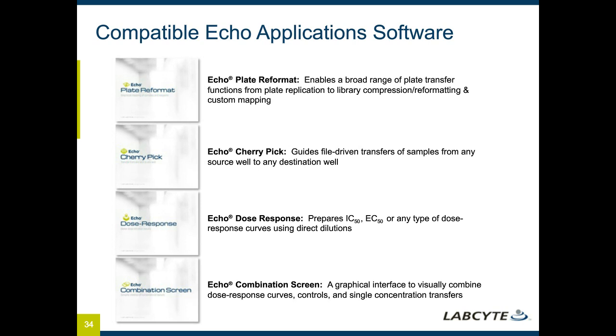And we have a software specific to Echo Dose Response, so it enables you to very quickly and easily create the different dilutions through that direct dilution process for your IC50 or EC50 types of experiments and generate those dose response curves depending on the number of points that you want and the concentrations that you determine are necessary. And then lastly, for situations where you're looking at the interaction between different drugs potentially, we have a software we call Echo Combination Screen, which enables the easy creation of protocols that not only enable dose response curves for a single compound or drug, but combinations of different drugs to be created within that and do that in a very seamless fashion.